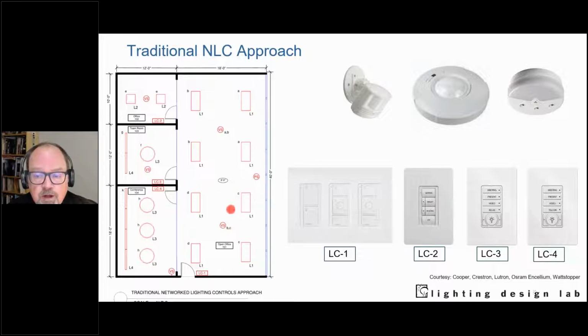These two are in primary daylight zone, these two are in secondary. So I have four zones of control here, controlling eight different luminaires. Those are then governed by vacancy sensors: vacancy sensor takes zones A and B, vacancy sensors C and D. And then I have a photocell that tells me how to dim the primary daylight zone and the secondary daylight zone.